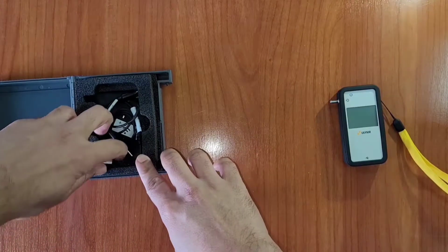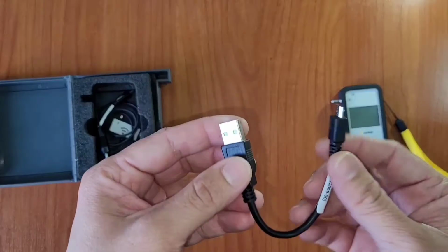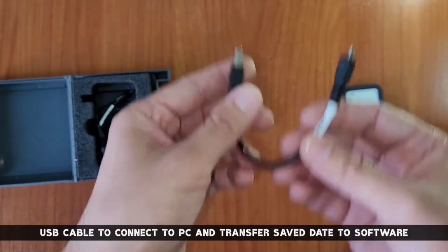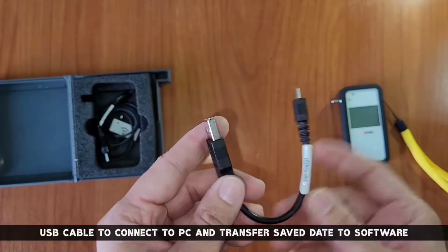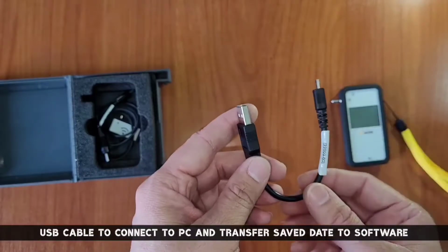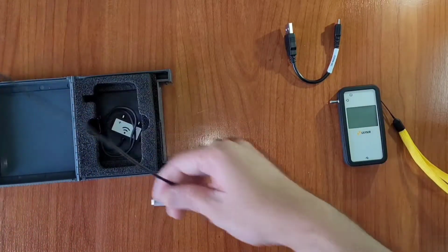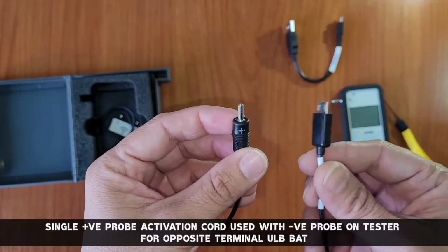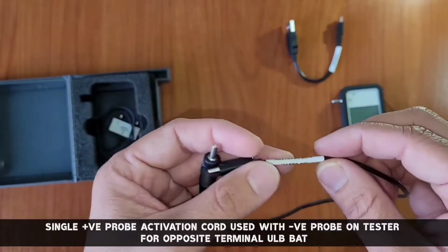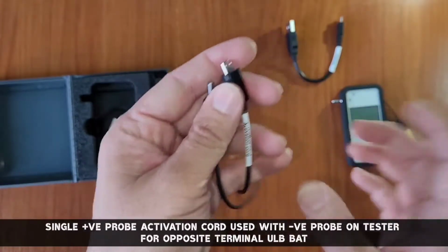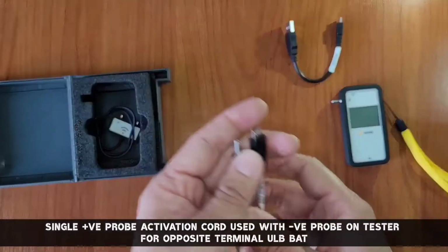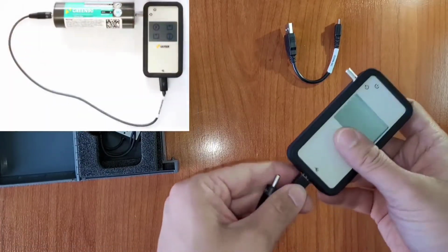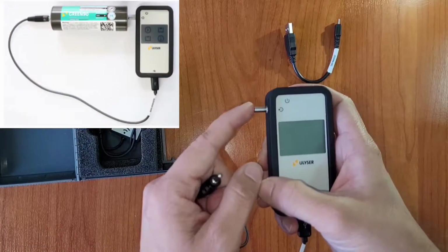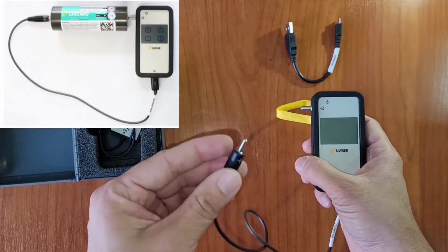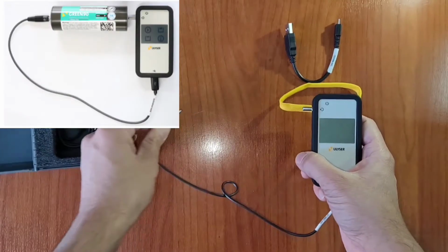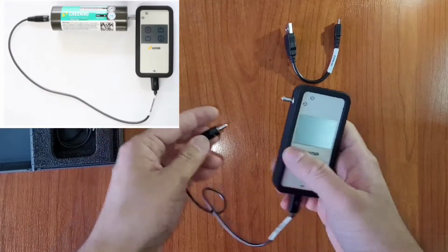We have got 3 cables over here. This is the normal cable with USB port so that you can connect it with the PC and we can transfer the data from our tester to the PC for the particular software. This is a single port, single probe type cable cord which has to be used with the battery which has got the terminal on the opposite side. So we'll connect this one, and then one probe we have to use with this one, connect with this negative side, and the positive probe will be connected on the positive side of the battery.